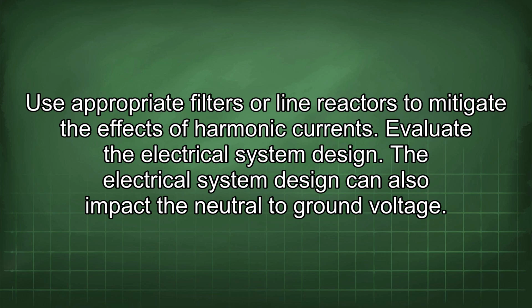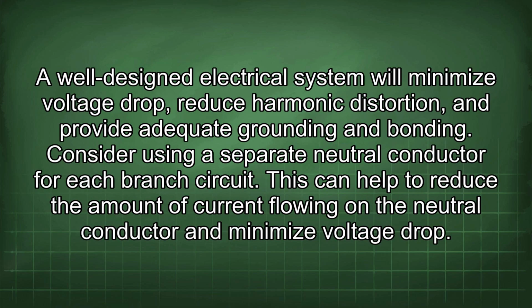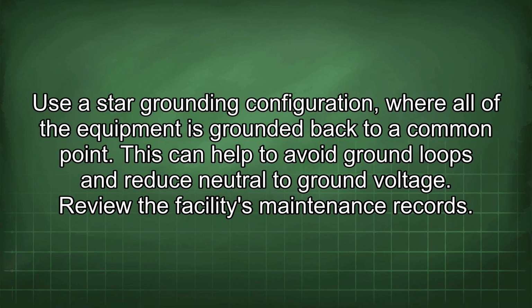Evaluate the electrical system design. The electrical system design can also impact the neutral to ground voltage. A well-designed electrical system will minimize voltage drop, reduce harmonic distortion, and provide adequate grounding and bonding. Consider using a separate neutral conductor for each branch circuit. This can help to reduce the amount of current flowing on the neutral conductor and minimize voltage drop. Use the star grounding configuration, where all of the equipment is grounded back to a common point. This can help to avoid ground loops and reduce neutral to ground voltage.